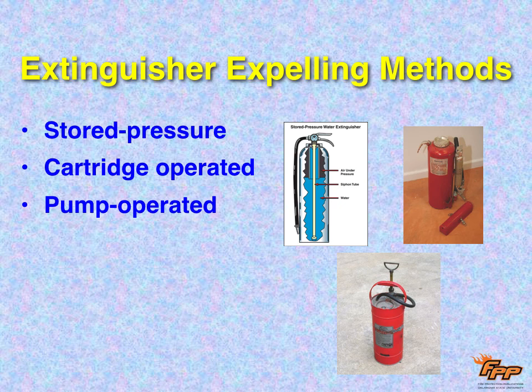Then there's cartridge operated. That's the top right picture, and that's a CO2 cartridge that's going to push out the dry chem that's in the bigger red portion of the extinguisher. Don't see very often pump-operated extinguishers. Wildland firefighters use pump-operated water extinguishers where they can use it out in the middle of nowhere. They fill a bag or the can, we preferred bags because they're lighter, with water, and then they have a little pump action and they can use it.